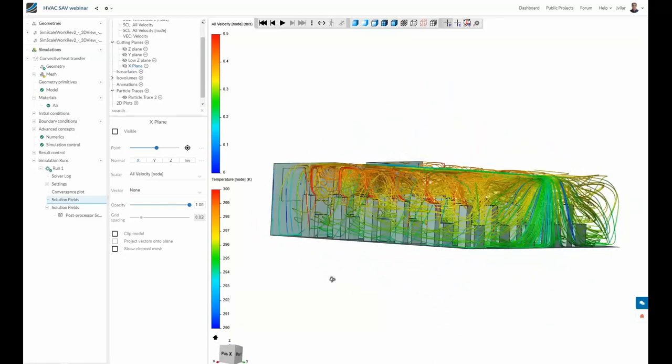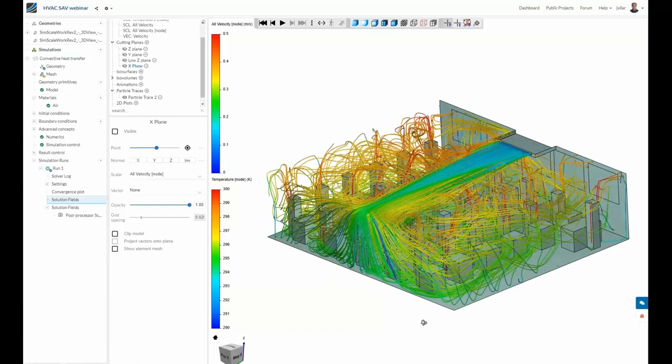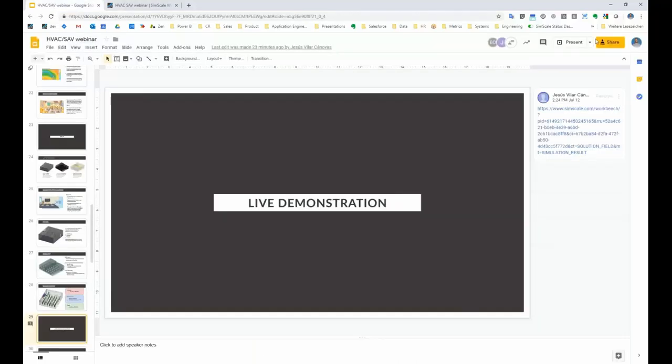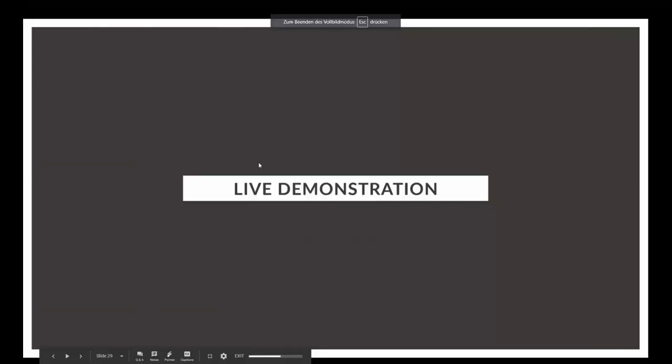So if you don't want to see anything else from here, we can move to the slides again and show a summary of the results. Yeah, I'm very happy with that. I was really pleased with the results we got because, I mean, generally, I tried to work in a very open manner. And I think the way we entered all our data into SimScale was very, I don't want to say honest, but, you know, it was genuine. All the inputs were the technical data that we had, the standard room conditions that you get in a British school. So, it was 60 meters squared, 31, maybe 32 occupants. We tried to make it as normal as possible. And then to see it come out with, you know, air distribution is great, temperature is great, no draft, that sort of thing, was brilliant.